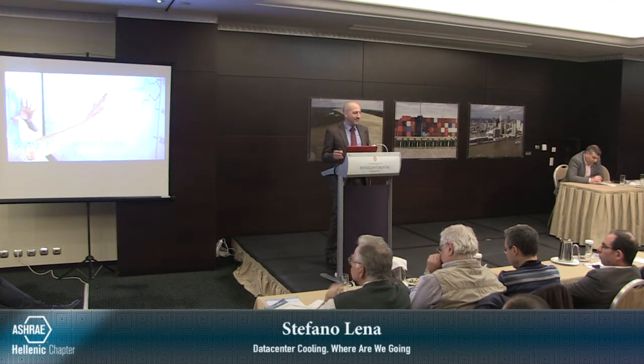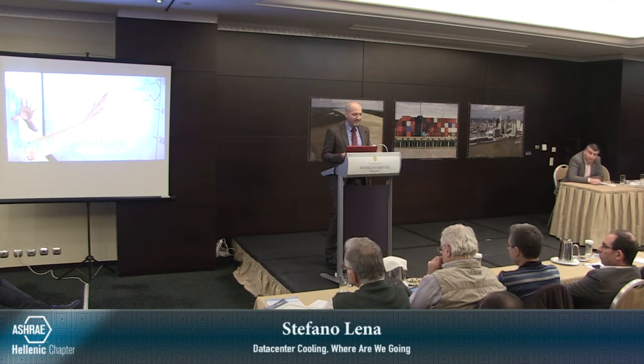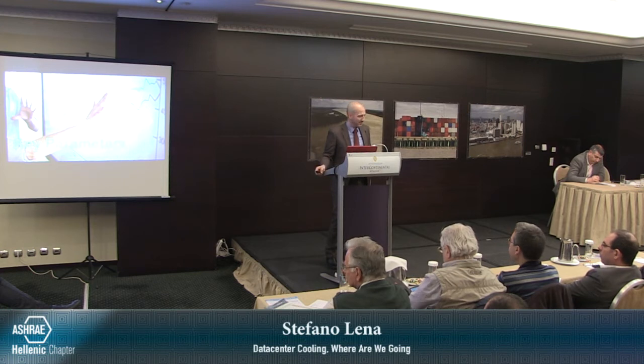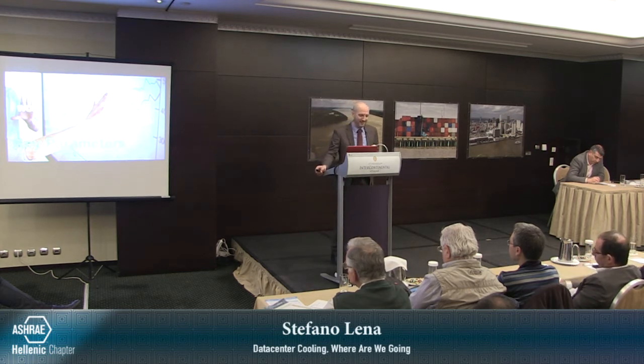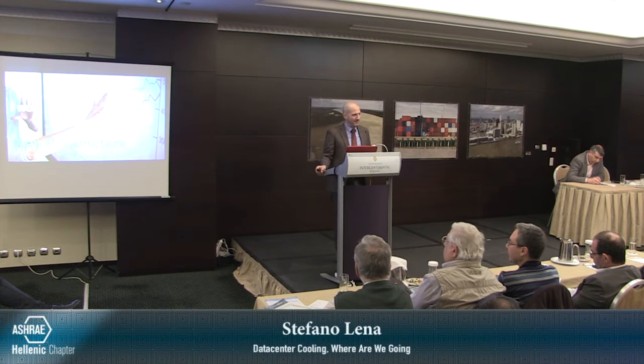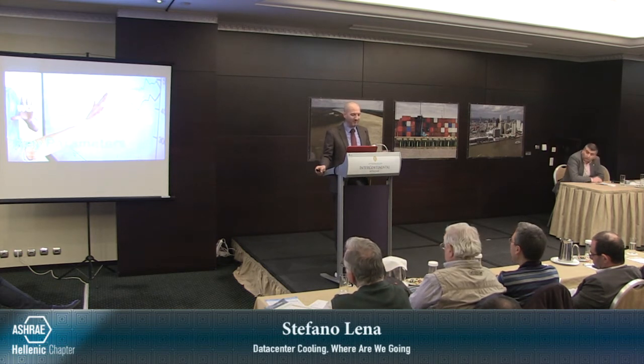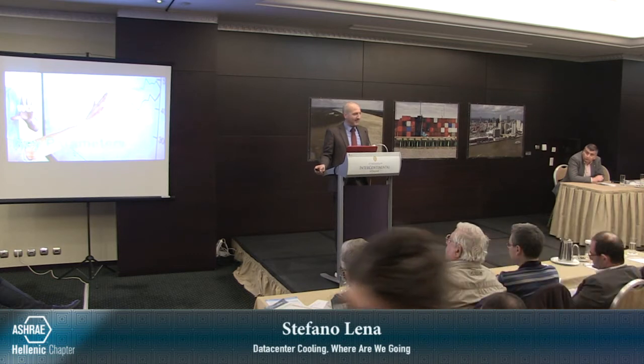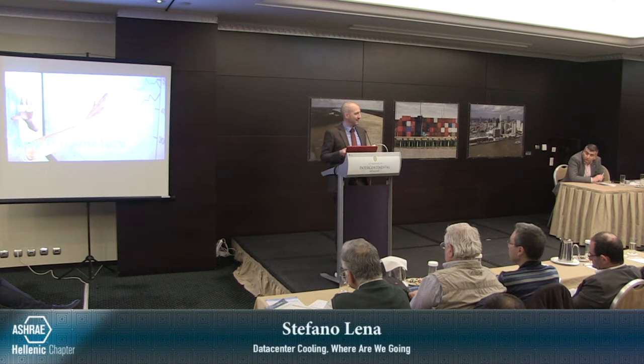How all those aspects are translated in numbers, because we as engineers are required to comply with numbers. And despite the fact that in the past we faced just a few numbers, today those numbers are much more. So we have a requirement written in terms of water usage, PUE or partial PUE. We have CAPEX and OPEX numbers. And all those numbers are not independent from each other. We are asked that all of them are related in the proper way from the customer and or the end user point of view.